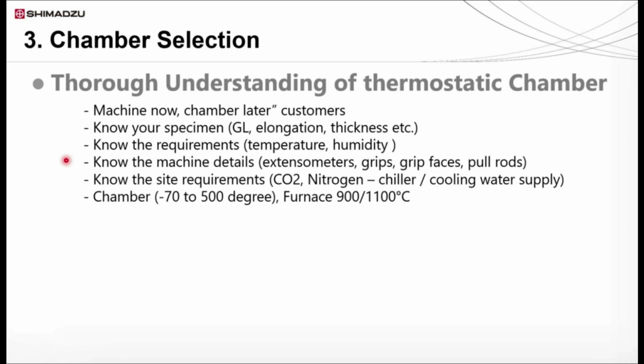Many years back, I remember a mistake of mine where I once supplied a chamber and a high temperature grip to one customer, but the grip faces I selected were normal temperature type, which the customer found very challenging to use inside the chamber. Sometimes chiller cooling water is also required, like for grip cooling, extensometer cooling, etc. If the chiller is not purchased separately, the customer may have to arrange a continuous cooling water supply in the lab. So discuss the chiller requirement with the supplier in advance.